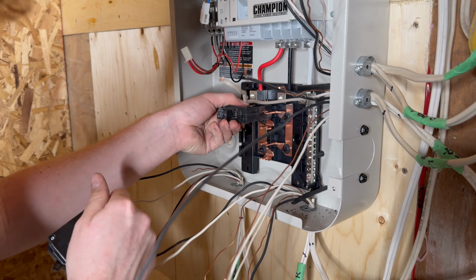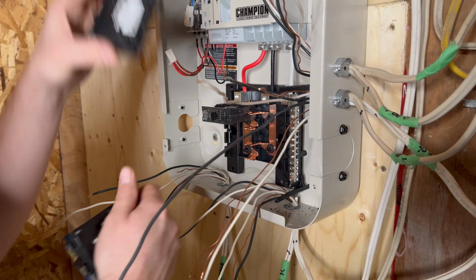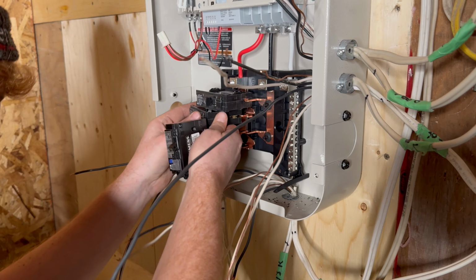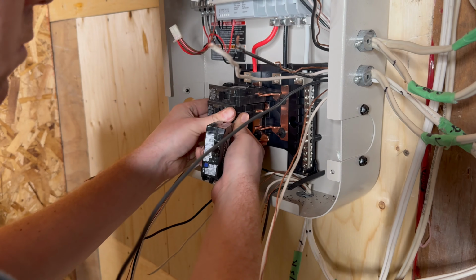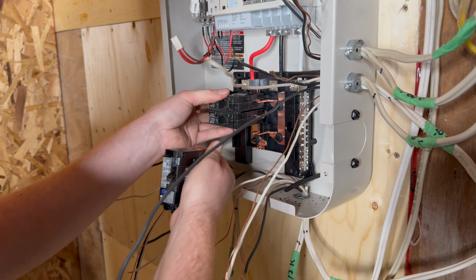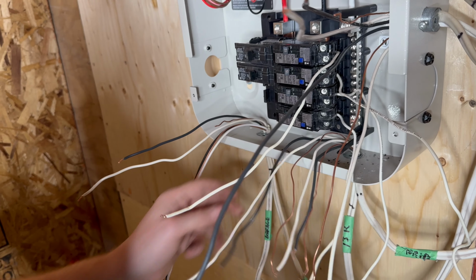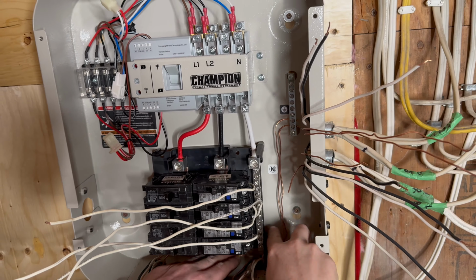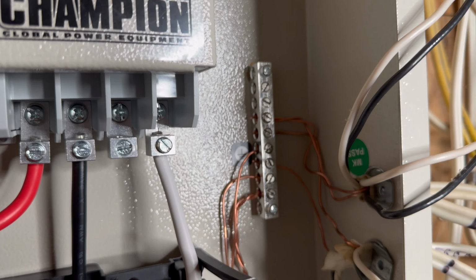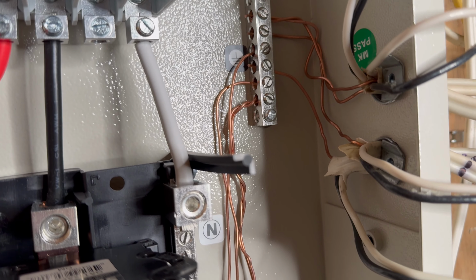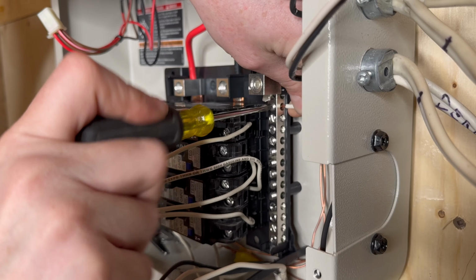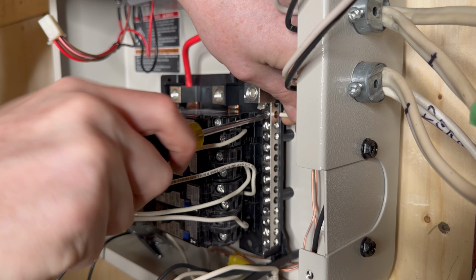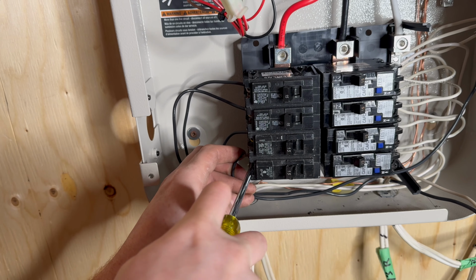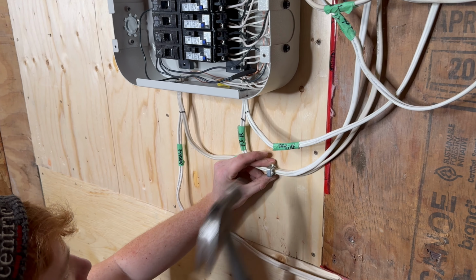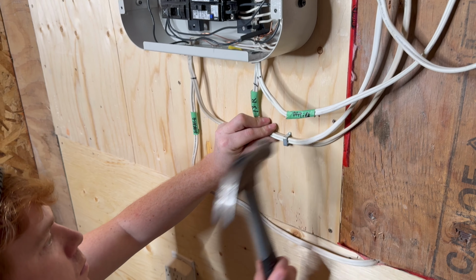With all the cables routed into the switch panel, it's time to install breakers in the appropriate places. And of course they need to match the power and safety requirements of the circuits that they're protecting. Continue work and complete all of the connections happening within the switch panel, all the connections related to circuits. So that would be ground, neutral, hot wires, and any additional wiring coming off the arc fault breakers. Finish up with the circuit cabling by reinstalling some staples to secure everything in a safe and neat way.